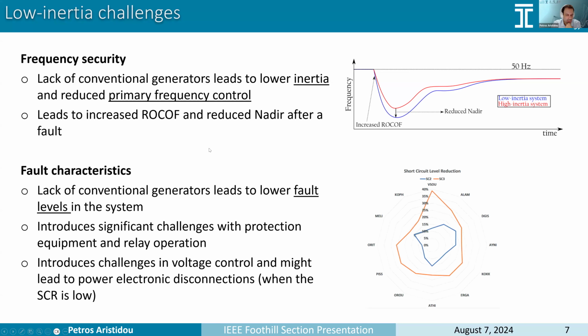Another big problem that arises is a change in the fault characteristics in the grid, because again, the lack of conventional generators leads to lower fault levels in the system. This introduces significant challenges to the protection equipment, relay operation, and coordination of the different protection schemes. It also introduces challenges in the voltage control that might lead to power electronic disconnections when the short circuit ratio is low in the system. We can see the figure on the right-hand side.